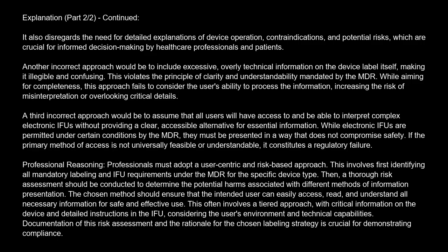Professional reasoning. Professionals must adopt a user-centric and risk-based approach. This involves first identifying all mandatory labeling and IFU requirements under the MDR for the specific device type. Then, a thorough risk assessment should be conducted to determine the potential harms associated with different methods of information presentation. The chosen method should ensure that the intended user can easily access, read, and understand all necessary information for safe and effective use.